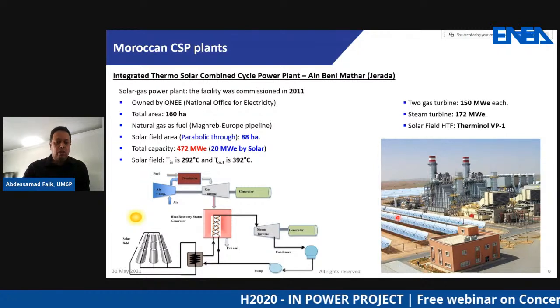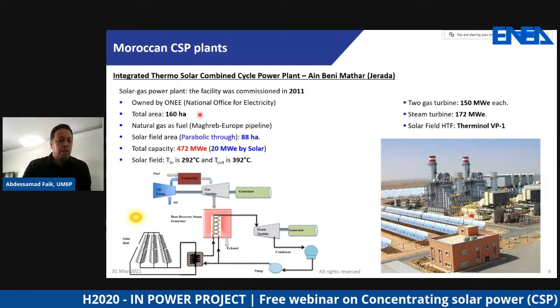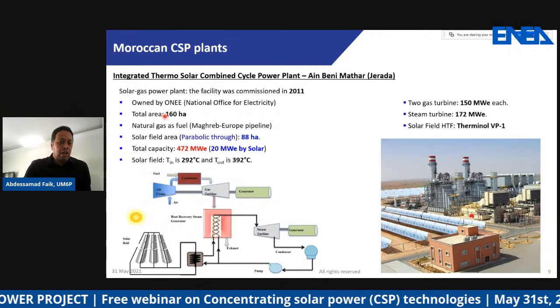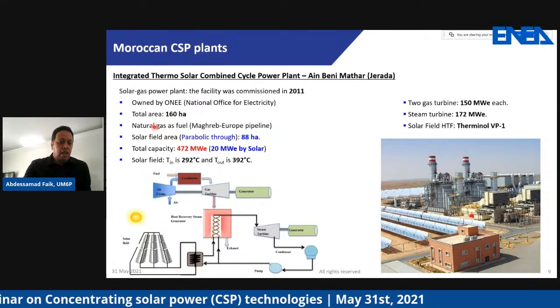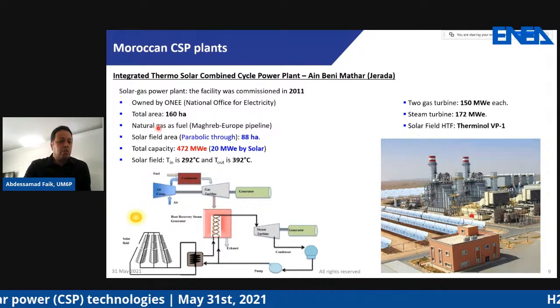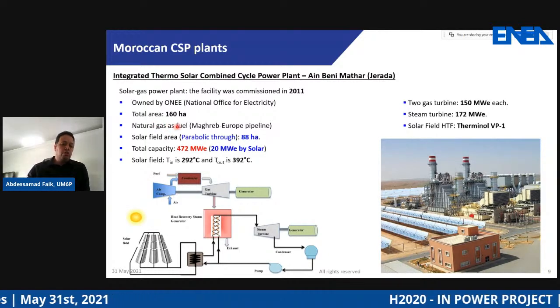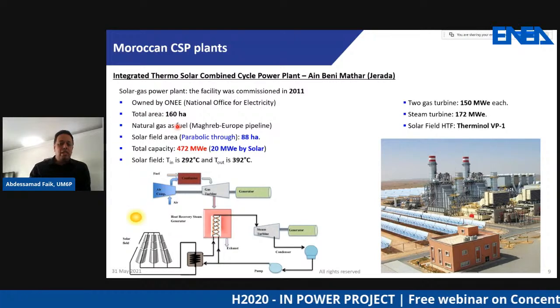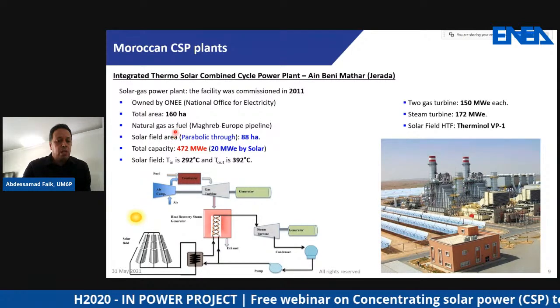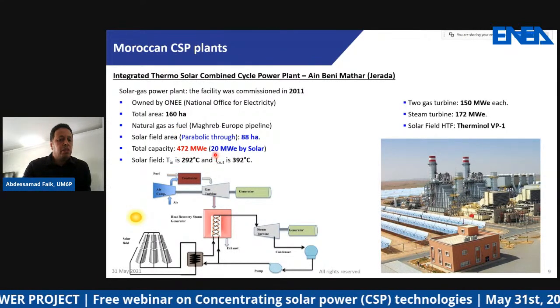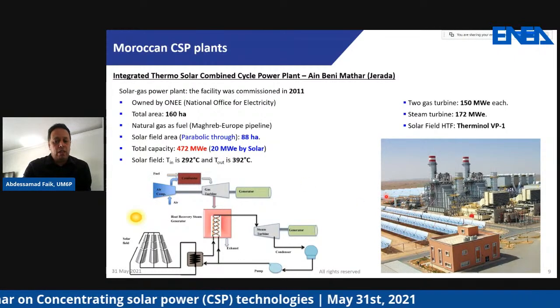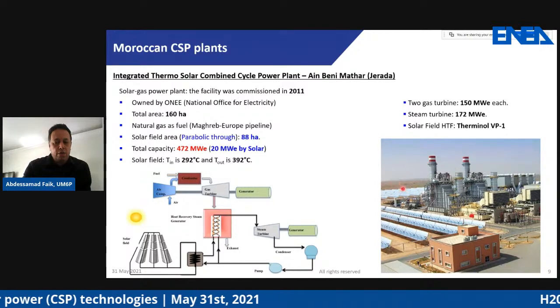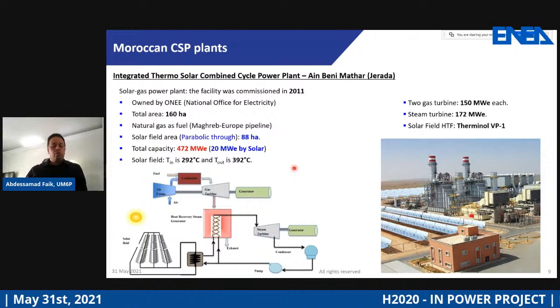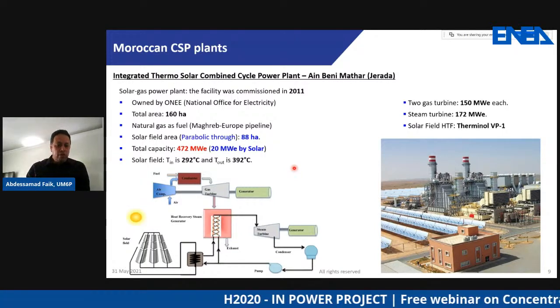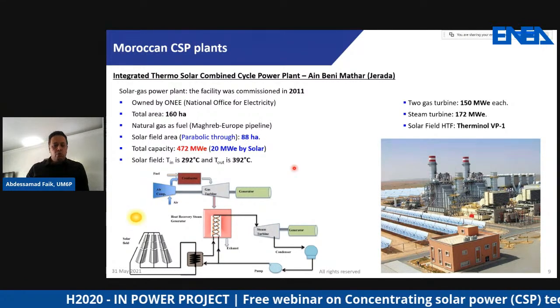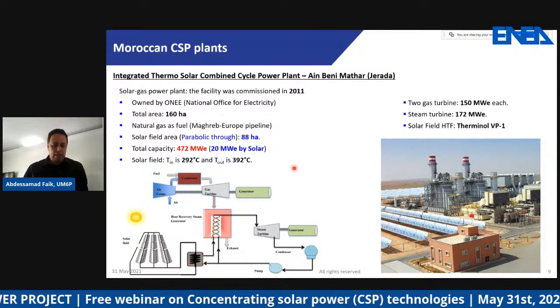This is why we call it a solar gas power plant. It is owned by the National Office of Electricity and occupies a total area of 160 hectares. This conventional power plant normally uses natural gas as fuel, coming from the pipeline from Algeria that feeds Europe, and Morocco taps this gas to produce electricity. That gives a production of around 472 megawatts, of which 20 megawatts is guaranteed by the solar field shown here. In this case, CSP is used to hybridize with conventional power plants in order to decrease their CO2 footprint.